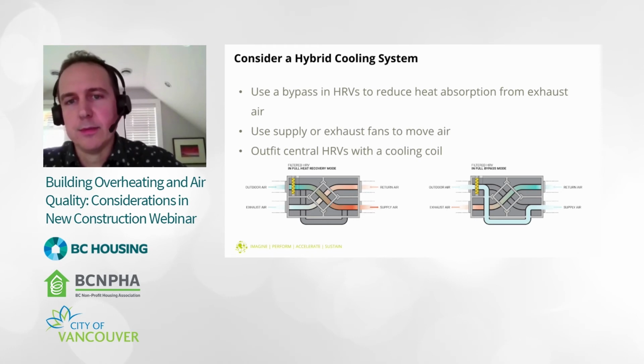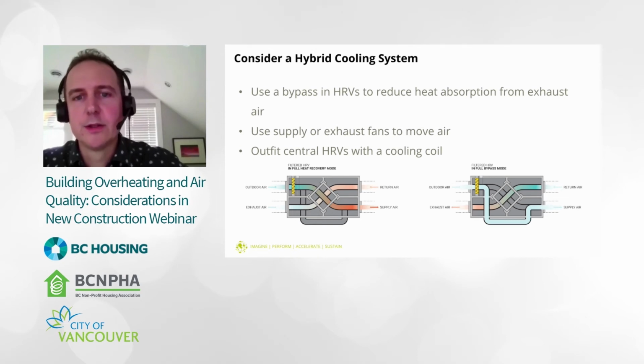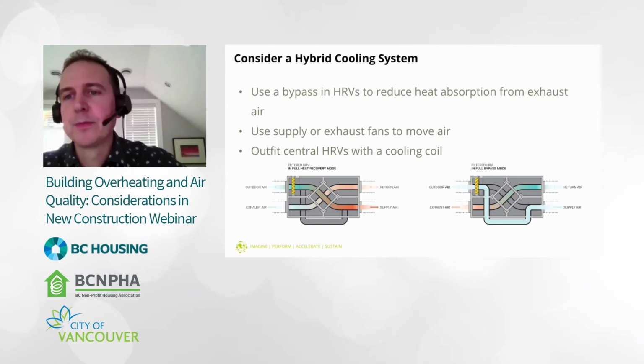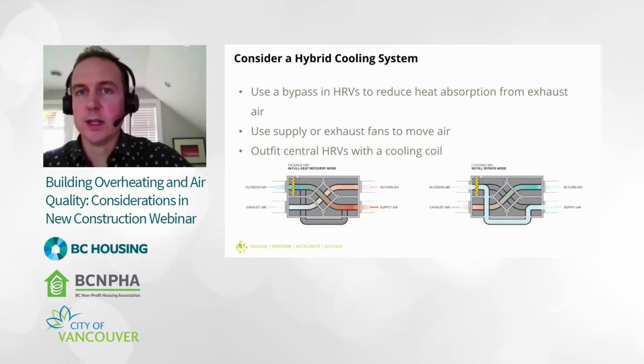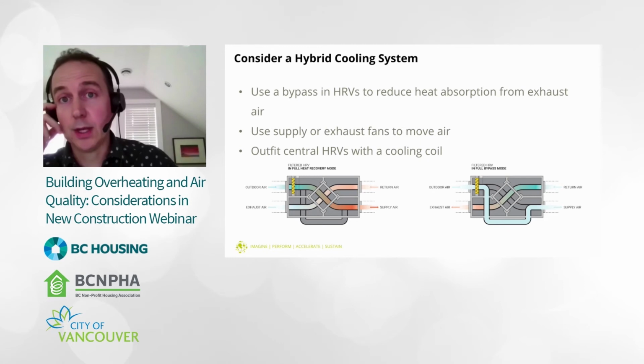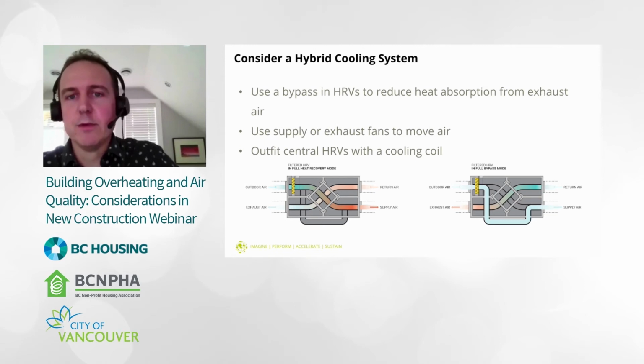So the image on the left here is the HRV, a heat recovery ventilator, in full heat recovery mode. Heat is transferred from the return air to the exhaust, to the supply air, to the outdoor air as it enters into the building. And then on the right, it's the same unit, but in full bypass mode. The outdoor air comes in, it actually bypasses around the heat recovery and goes straight to the indoor space. And the outdoor temperature, typically in shoulder seasons, is very effective at mitigating overheating and delivering good thermal comfort.